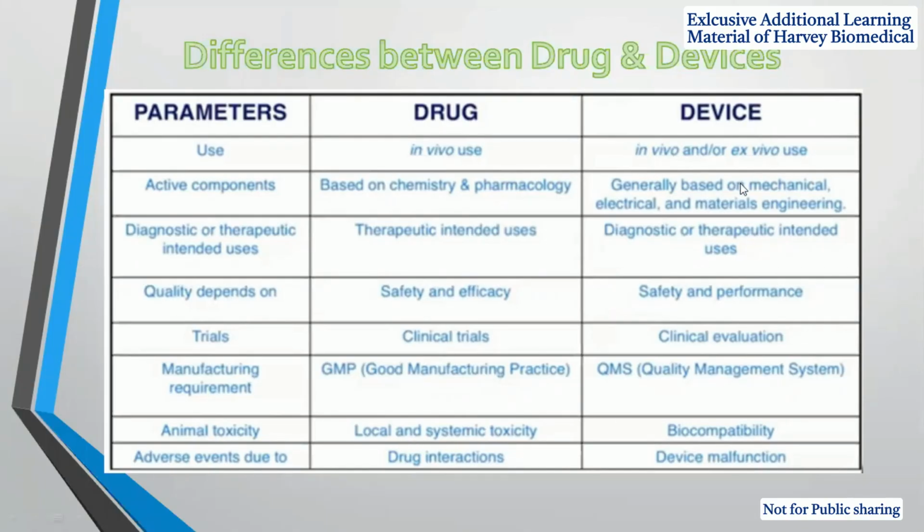Why are we doing biocompatibility for the device? The device is going into the human body, and we have to verify which organ it is going to, what the intended use is, and where we are going to install the device or where it is touching the human body. Accordingly, we have to check the biocompatibility and make the biocompatibility evaluation report.